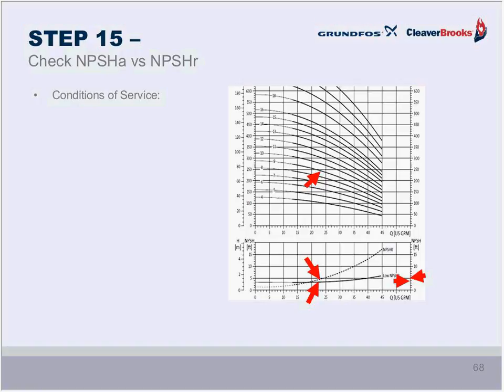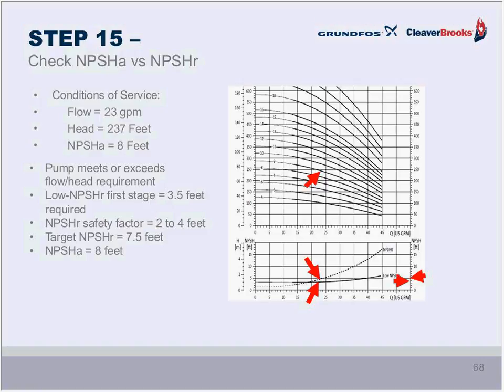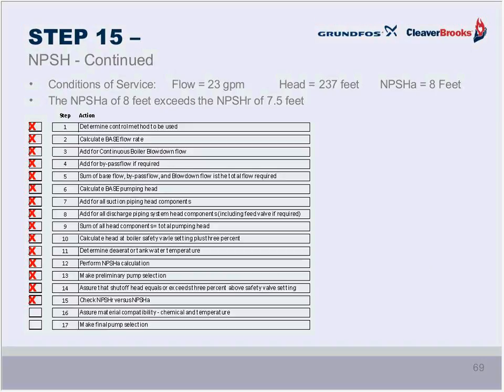You really need to consider going to the low NPSH design, which is indicated by that lower solid black line where we have about 3.5 feet of NPSHR. When you add the full 4 feet of conservative safety factor to that, we still only have 7.5 feet required. It's less than the 8 available, and that pump should not experience cavitation at the duty point. Okay. So we determined that there's the math on all of that, which you can take a look at later, and that pump does meet our requirement. We can tick that off the list because the requirement is less than the available.